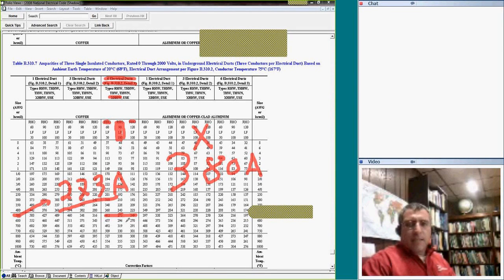Think about this. I teach engineers all the time, guys. I just wanted to emphasize this particular one because it's really interesting. Don't overlook this when you put things in underground ducts in this configuration. For ampacity you can't just use 380 for 500 kcmil. A lot of people, Eric, my friend, go 380 and okay, 380 across. You have to use either these configurations or you have to use an ampacity calculation software.